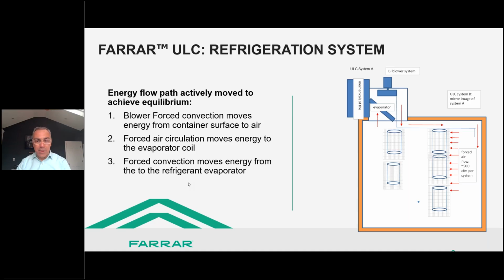cubic foot per minute, which moves the energy to the evaporator much more quickly than a natural convection cold wall system. From there, the energy is absorbed by the refrigeration evaporator and circulated back to the space to repeat the cycle. This system, of course, consumes a higher amount of energy than a natural convection cold wall freezer would, but only while there's a significant heat load, such as a door opening or added material. And that difference is really that blower motor.